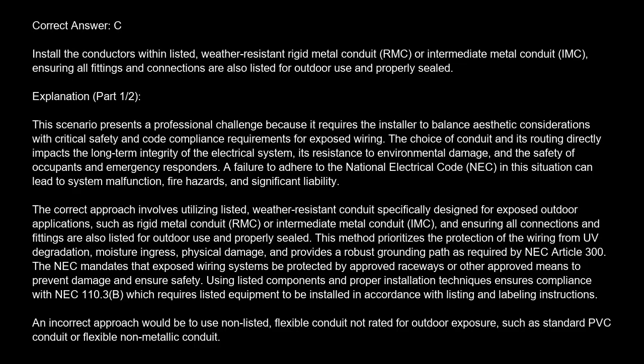The correct answer is C. Install the conductors with listed, weather-resistant rigid metal conduit RMC or intermediate metal conduit IMC, ensuring all fittings and connections are also listed for outdoor use and properly sealed. Explanation. This scenario presents a professional challenge because it requires the installer to balance aesthetic considerations with critical safety and code compliance requirements for exposed wiring. The choice of conduit and its routing directly impacts the long-term integrity of the electrical system, its resistance to environmental damage, and the safety of occupants and emergency responders.